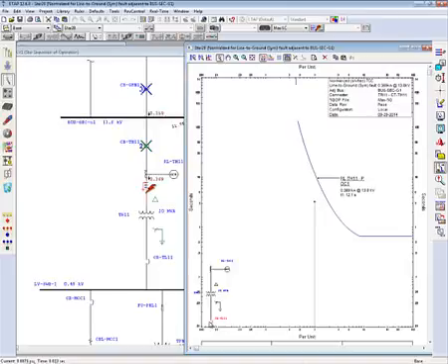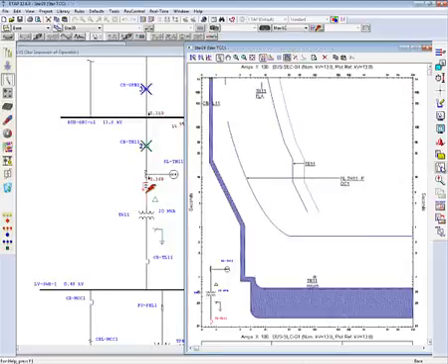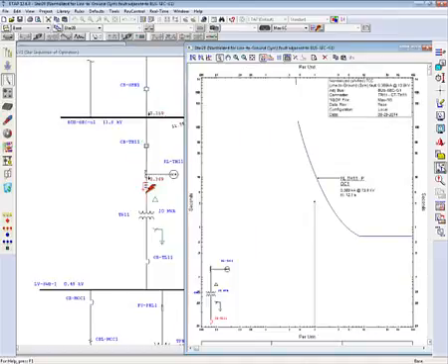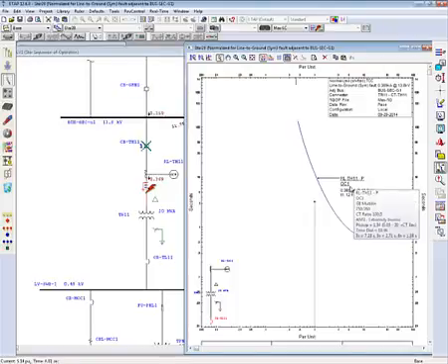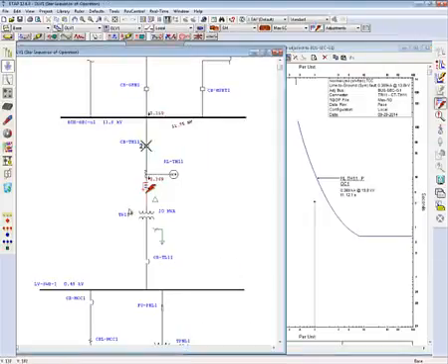Because of the minimum fault current setup, it's not plotted in the normalized view and correctly depicts the behavior of the protective device. I can go from normalized to my regular star view and see both the curves. But for the normalized star view, as it's based on actual through fault condition, the CBTL11 curve is not shown on the normalized TCC view.